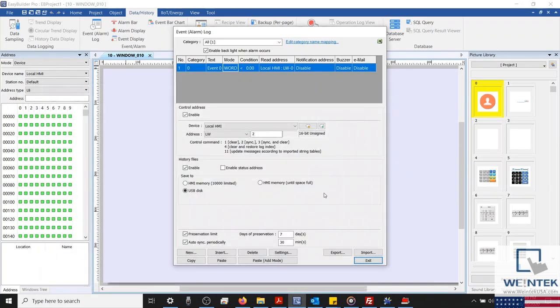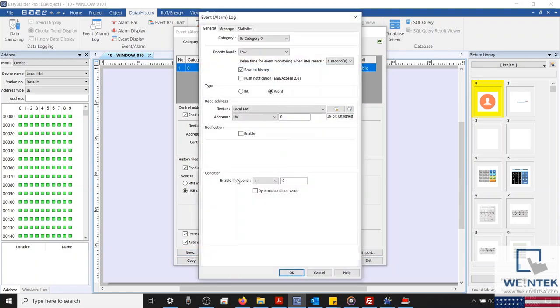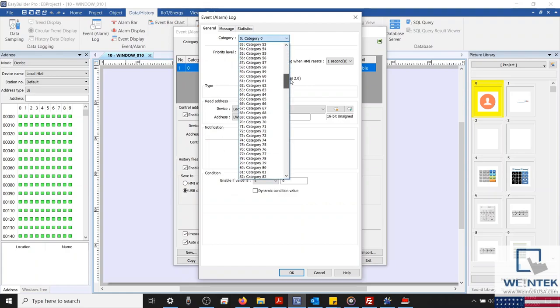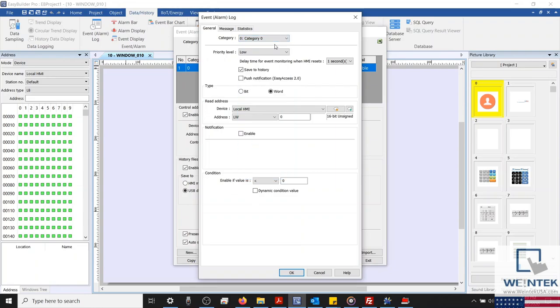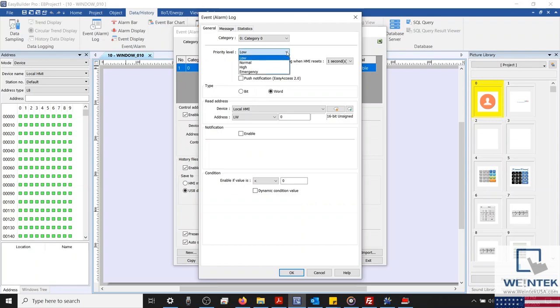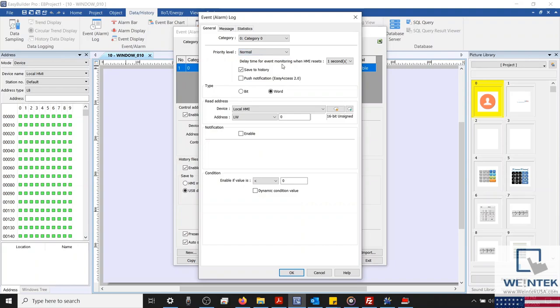With that information covered, let's move forward and create our first event log. To do this, I'm going to select New, and our Event Settings menu will appear. At the top of our Alarms configuration, we can assign it to a specific category. As I explained before, alarm categories can be used to help organize our event log, or allow us to configure a display object to show only certain alarms from specific categories. Underneath this, I can configure the priority of our alarm. The priority of an alarm will allow us to establish the order in which events are sent as push notifications, how they are sorted within our alarm bar or alarm display object, and even allow an alarm with an emergency priority level to display a small notification in CMTViewer when viewing multiple projects simultaneously.